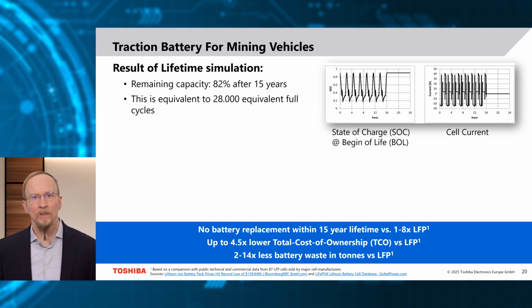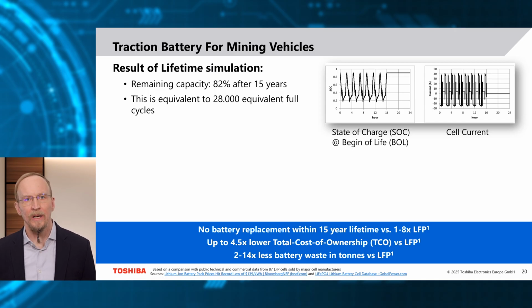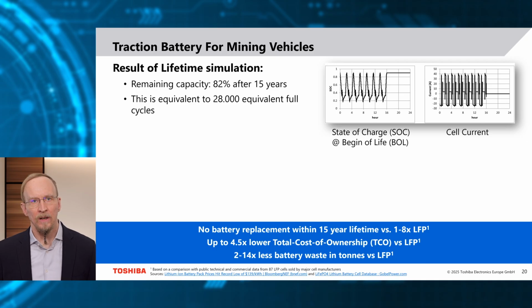We compared the result with 87 commercially available LFP cells. For the estimation, we used publicly available data and made reasonable assumptions. The result of the comparison is that no battery replacement is necessary within 15 years with SCiB LTO cells, whereas 1 to 8 replacements are needed with LFP cells. This results in an up to 4.5 times lower total cost of ownership and 2 to 14 times less battery waste in tons. Further applications will now be explained by Sacha.